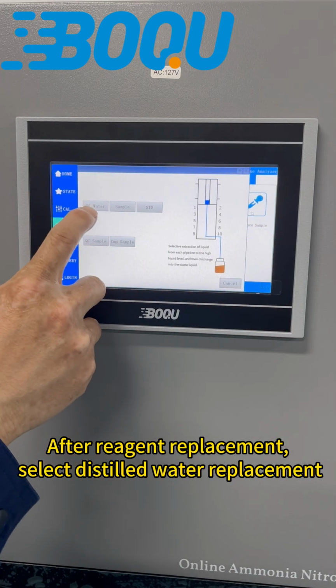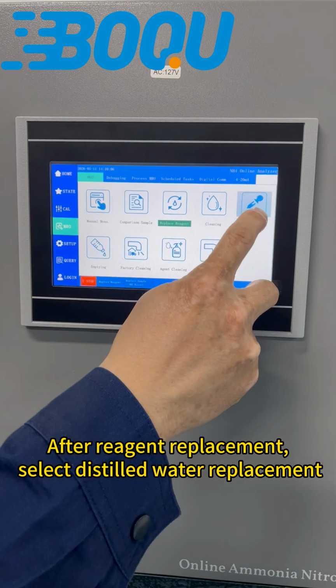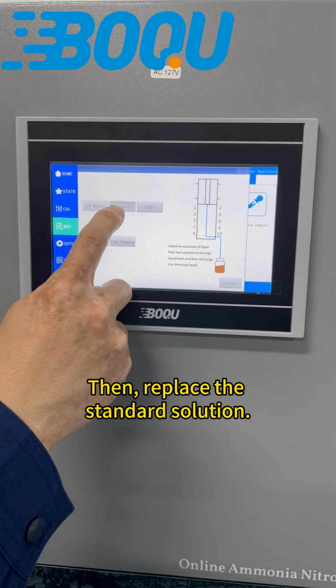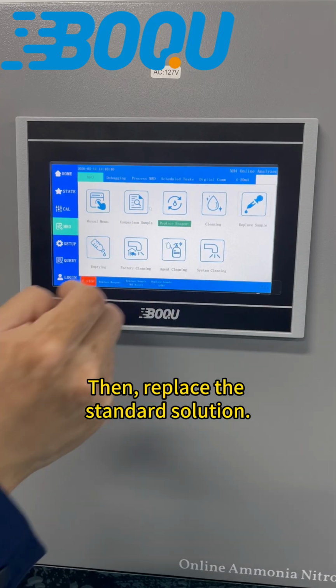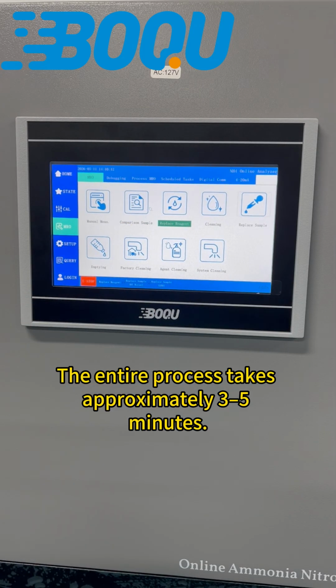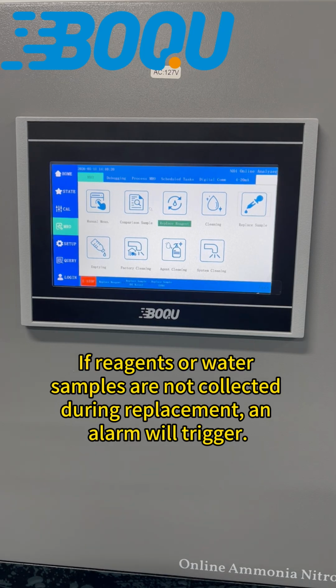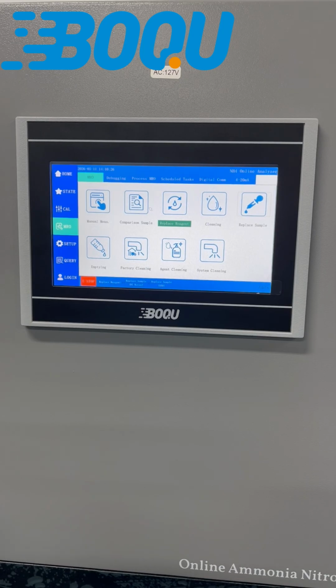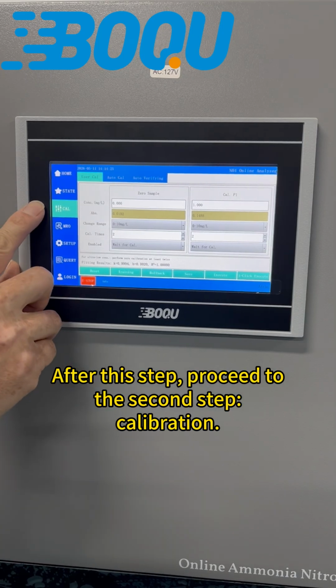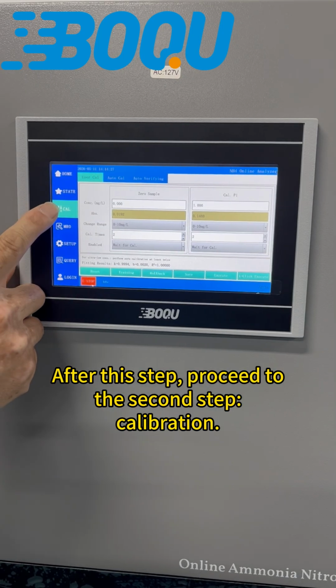After reagent replacement, select distilled water replacement. Then, replace the standard solution. The entire process takes approximately 3 to 5 minutes. If reagents or water samples are not collected during replacement, an alarm will trigger. After this step, proceed to the second step, calibration.